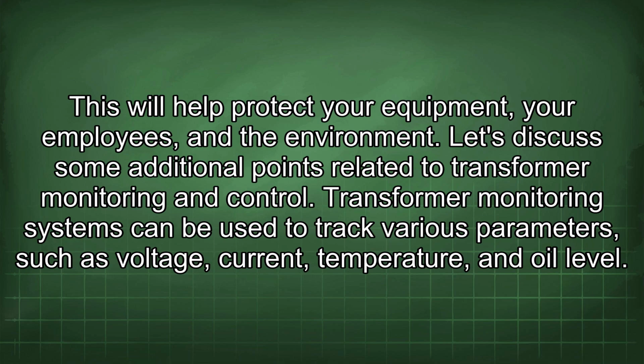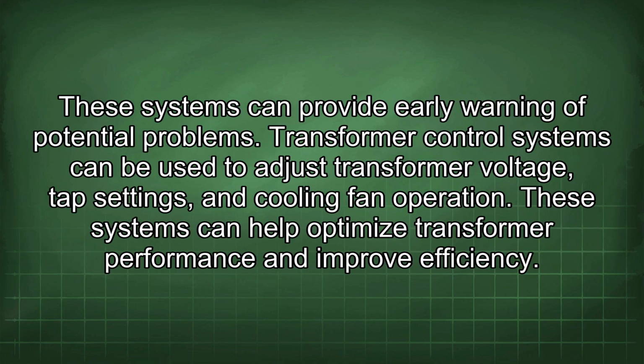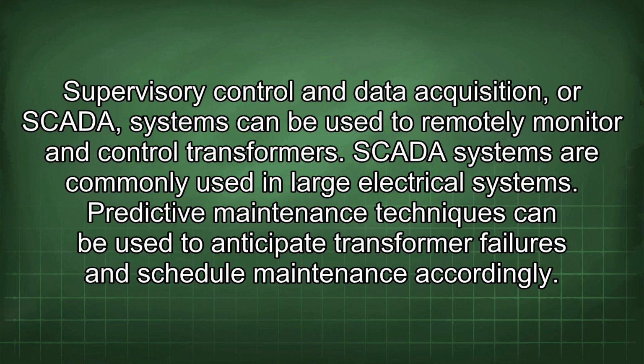Let's discuss some additional points related to transformer monitoring and control. Transformer monitoring systems can be used to track various parameters such as voltage, current, temperature, and oil level. These systems can provide early warning of potential problems. Transformer control systems can be used to adjust transformer voltage, tap settings, and cooling fan operation. These systems can help optimize transformer performance and improve efficiency. Supervisory control and data acquisition, or SCADA, systems can be used to remotely monitor and control transformers. SCADA systems are commonly used in large electrical systems.